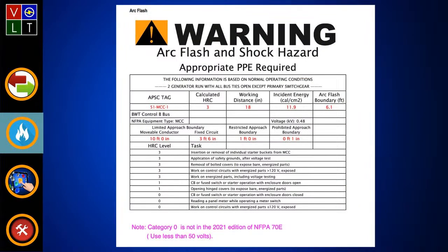Now we should always look at our warning labels. We know that 110.16 of the NEC warns about the arc flash, along with 110.21 and 110.25 - all those go together for the NEC. But we go to 130.5H and 70E, and that is a label that has to be put on by the owner. Those labels in the NEC - 110.16, 110.21, 110.24, and 110.25 - are labels the electrician doing the work has to put on. But you read these labels, and you can see for certain levels and certain tasks we have the numbers listed there. I listed those because those are tasks we usually do as electricians.